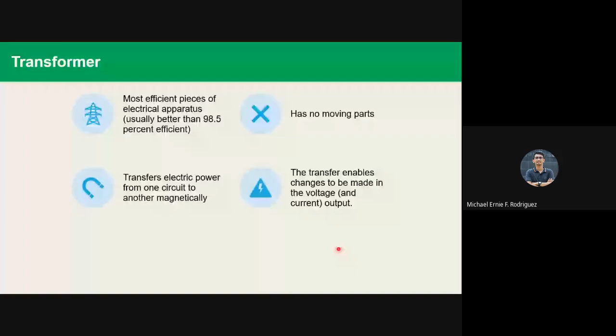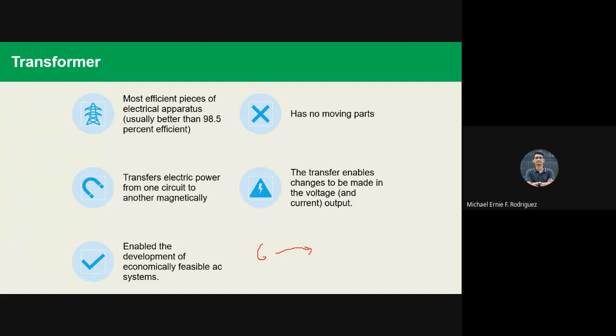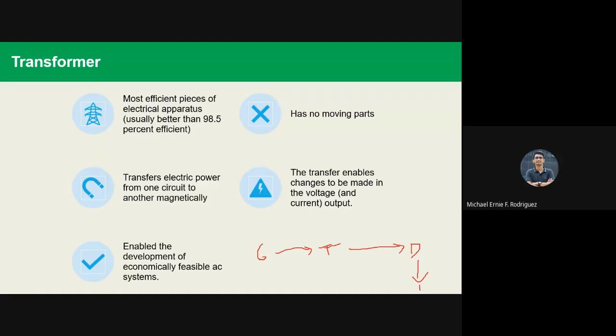It enabled the development of economically feasible AC systems. The use of AC systems became economical because you can step up the voltage from generation, raise the voltage going to transmission, so that the losses are lower. Then you step it back down at distribution for the safety of consumers and for final use in homes. That's the job of the transformer.